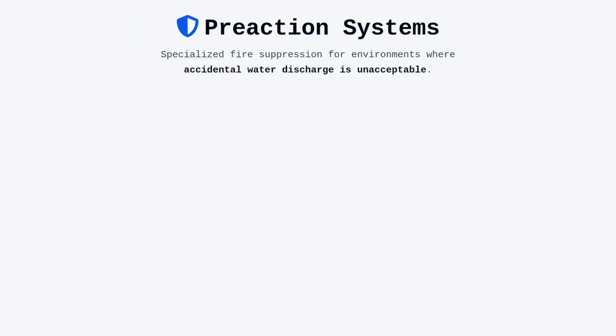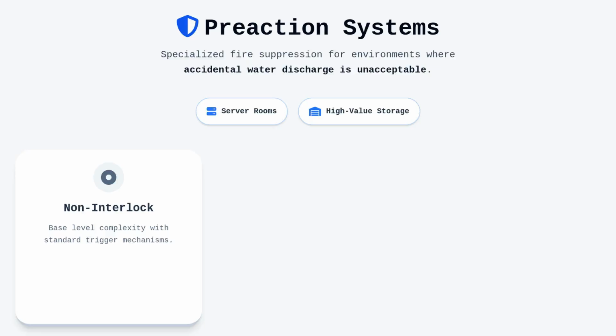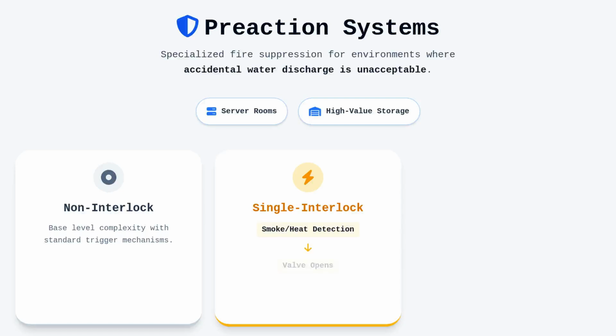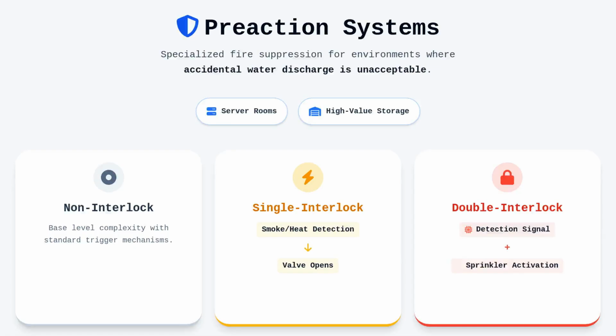Pre-action systems offer a more nuanced approach, specifically designed for occupancies where the risk of accidental water discharge is unacceptable, such as server rooms or industrial high-value storage. These systems are categorized as non-interlock, single interlock, or double interlock, based on the complexity of their release mechanism. In a single interlock system, the valve opens upon the activation of a smoke or heat detection device, independent of the sprinkler heads themselves. A double interlock configuration adds an extra layer of security by requiring both an automatic detection signal and the physical operation of a sprinkler head before water is admitted into the piping.